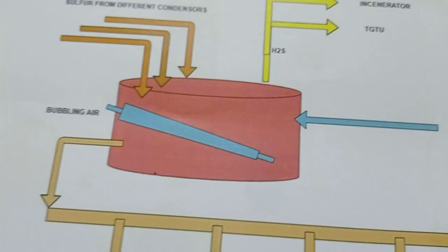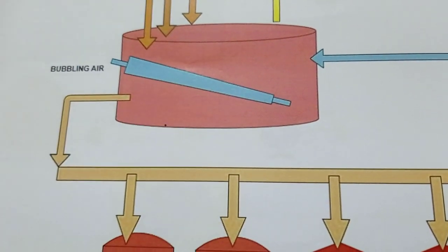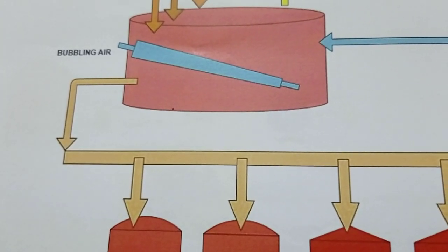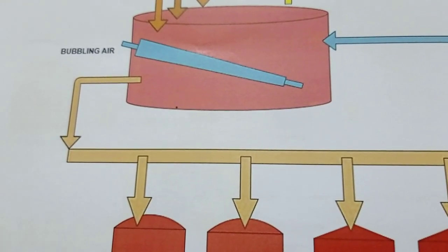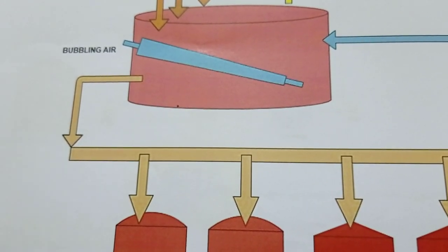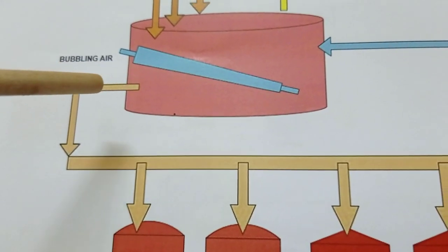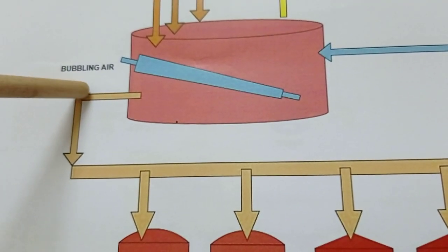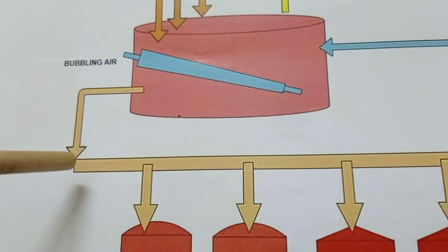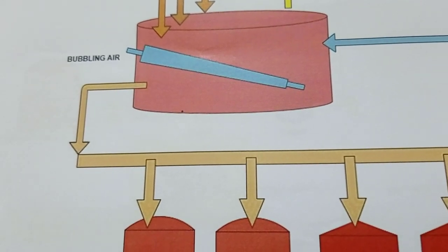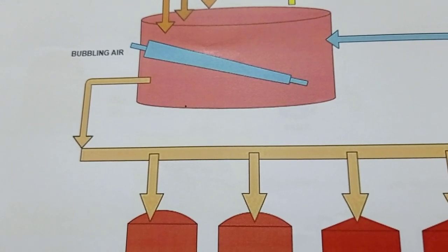Depending upon that, whatever sulfur is collected, all these pipes are steam jacketed. A steam jacketed pipe is nothing but a pipe within a pipe. For example, take one pipe and inside it one more pipe. Inside the pipe sulfur will go, and outside there will be a steam provision. Steam will go continuously. This is how we transfer sulfur. But here we have a bend, and after that we will have a connection here, so for that we will add a flange. But when we connect pipe to pipe, there may be chances that sulfur solidification takes place.